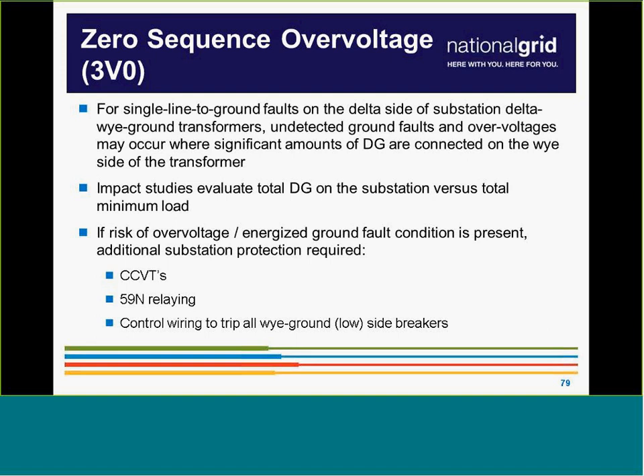So basically, to simplify it, if you have a delta high side transformer, if you look through the sequence networks of how the DGs on the distribution system feed into a fault on transmission, they can't see what's going on on the transmission system. Since they can't see it, we need to install zero sequence overvoltage protection, which is basically looking at quantities at the transmission side where you have a shift in your neutrals, and making sure that you trip off all of that generation from the low side of that distribution substation for that ground fault. So on a typical system, you'll have maybe one or two ends, and then you'll have your distribution substation with your delta high side transformer.